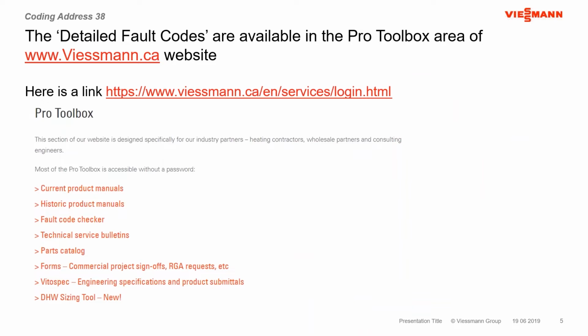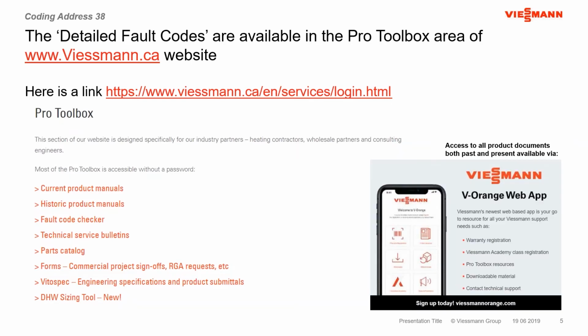But in order to get those diagnostic fault codes, and the detail of those fault codes, we need to access the technical service bulletin that's available for these particular boilers. To access that, you've got a couple of options. You can go to our website, Viessmann.ca, where we have our Pro Toolbox area. In that Pro Toolbox area, if you click on it, you'll have the current product manuals, historical product manuals, fault code checker, and the technical service bulletin area available there.